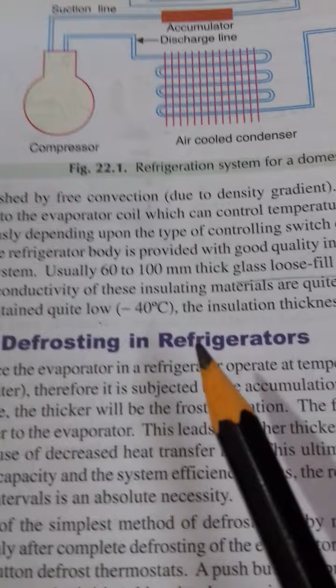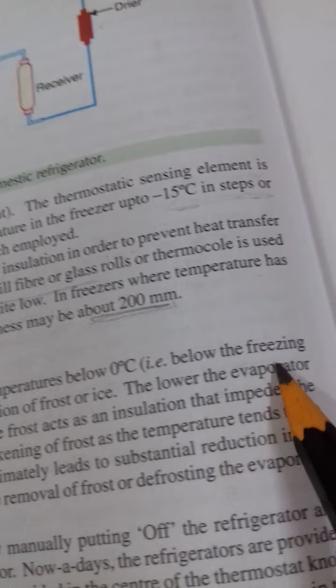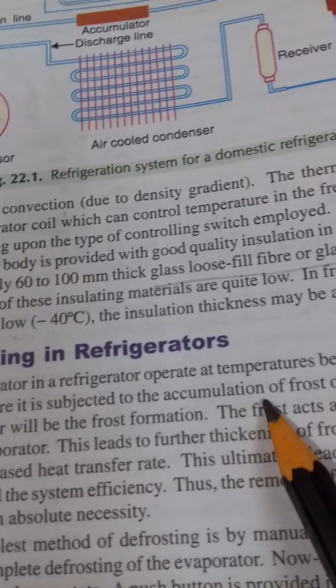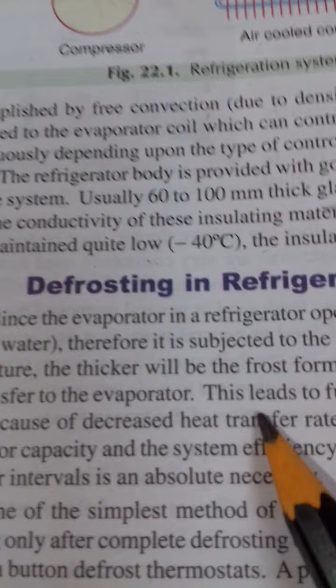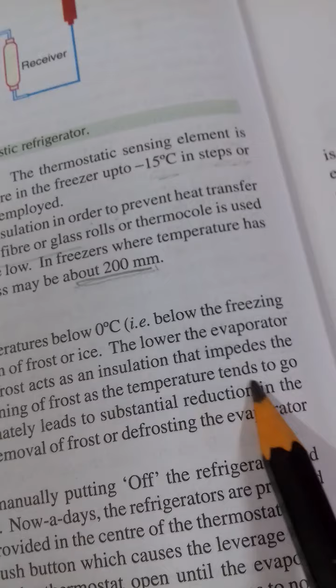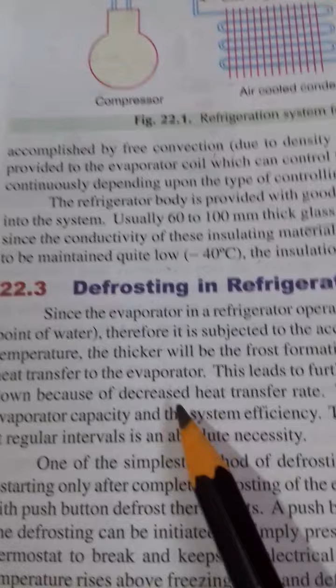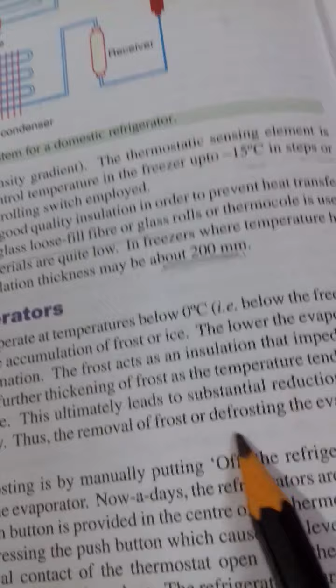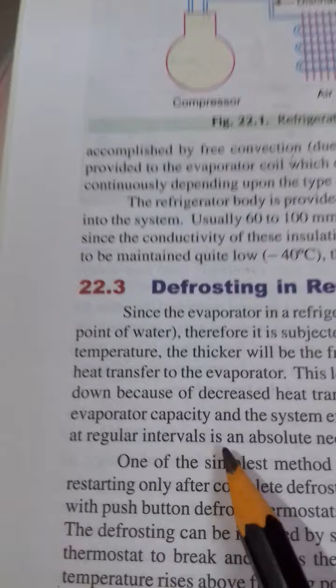Okay. Now, defrosting in a refrigerator. Since the evaporator in a refrigerator operates at a temperature below the freezing point of water, it is subjected to accumulation of frost or ice. The lower the evaporator temperature, the thicker the frost formation. The frost acts as an insulation that impedes the heat transfer to the evaporator. This leads to further thickness of the frost as the temperature tends to go down because of the decreased heat transfer rate. This ultimately leads to a substantial reduction in the evaporator capacity and system efficiency. Thus, the removal of frost, or defrosting the evaporator at regular intervals, is an absolute necessity.